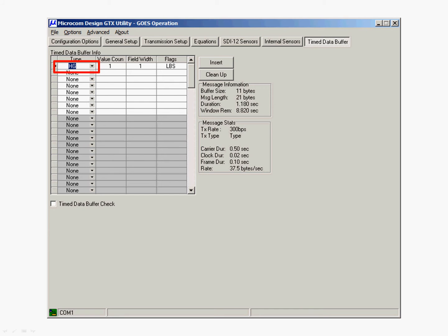We can change the value count from 1 to 24. Since we're taking a measurement every 5 minutes, 1 hour's worth of data will be 12 measurements. And if we want the past 2 hours worth of data, that has to be 24 measurements. So that's why we're changing the value count from 1 to 24 to get the past hours and the previous hours measurements in every transmission.